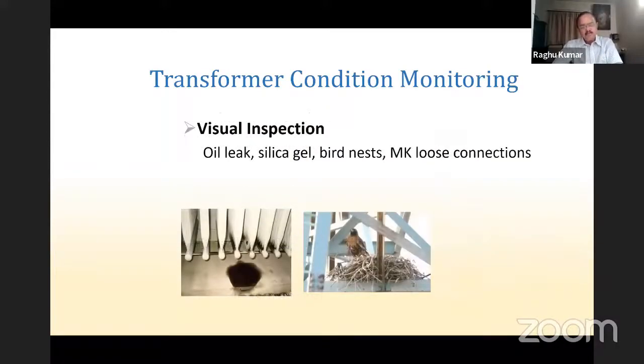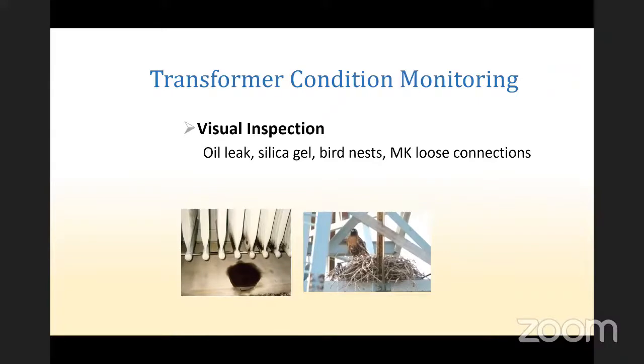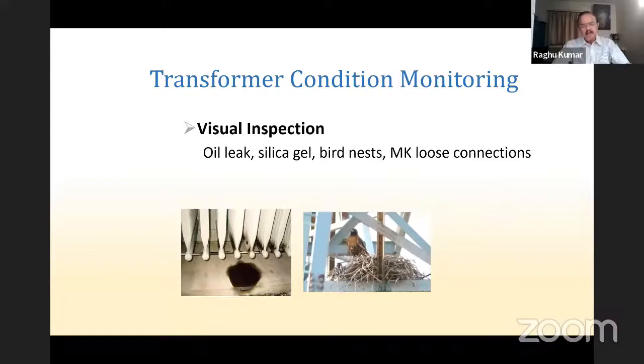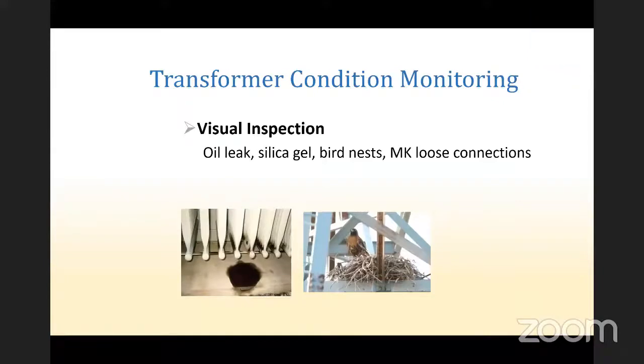Visual inspections can find defects like oil leaks, bird nests, marshalling kiosk issues, loose connections, etc. There was one case in Qatar where a visual inspection for an oil leak saved a bushing. It was a 315 MVA transformer, and during the visual inspection, it was noticed that oil was coming out of a bushing's test tap, and the leak was a bit serious. Immediate action was taken, and further inspection was carried out, and it was found that the bushing was defective and needed to be replaced.